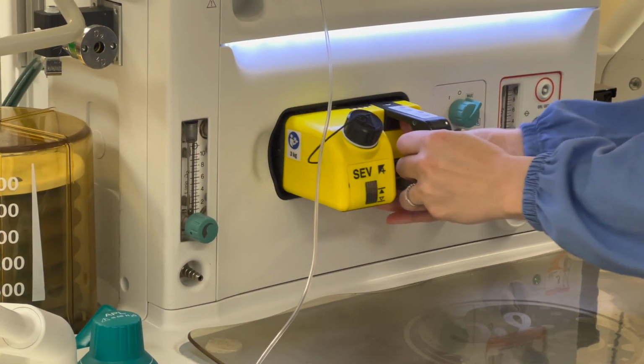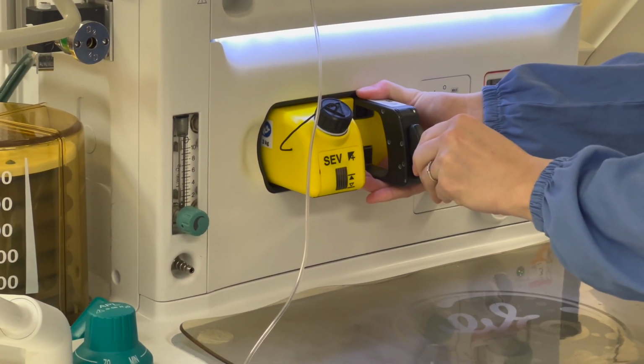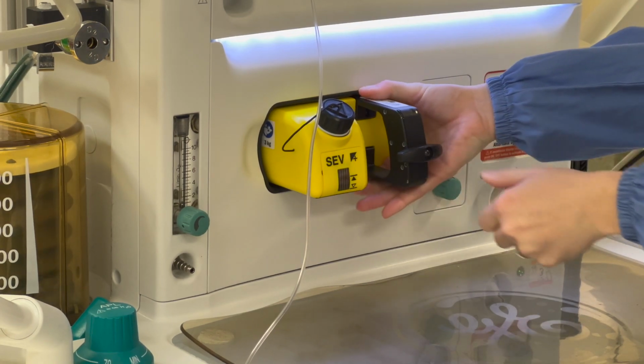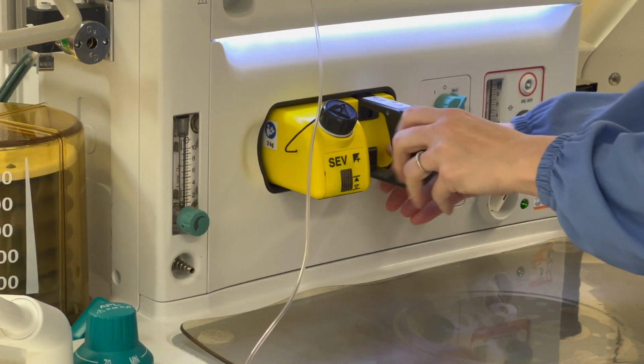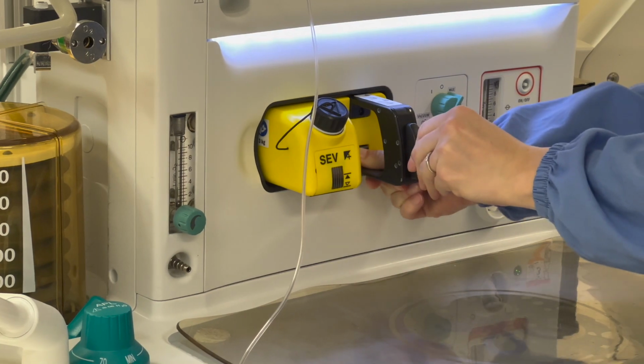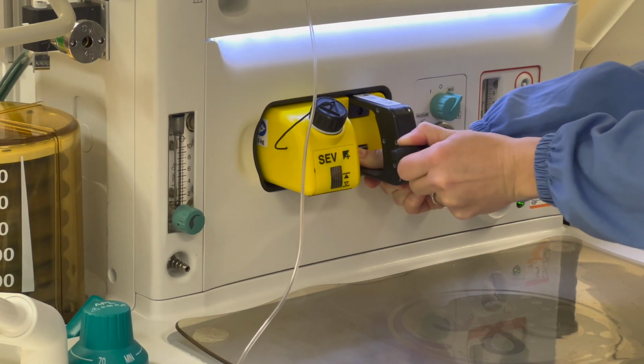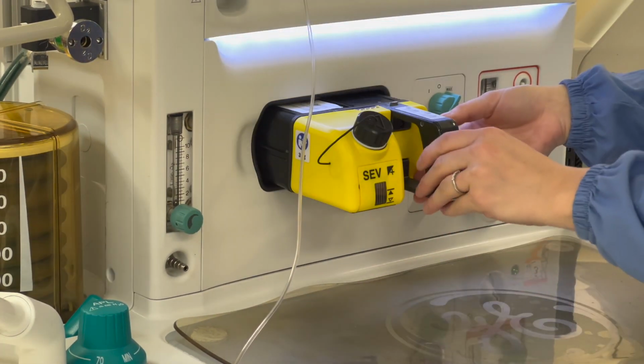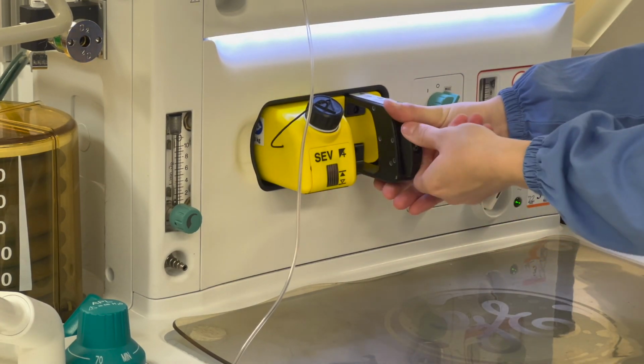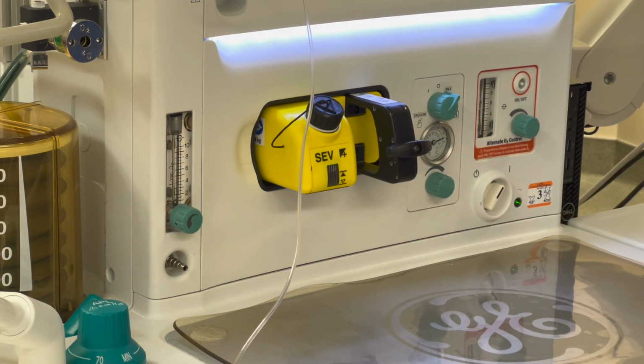One thing you may encounter is a cassette that doesn't fully engage. As you notice here, it slides back as you try to lock it in place. This won't be fully connected to the anesthesia machine, and it won't deliver anesthetic gases, and it'll be a potential for leak later on. Give it a firm push and then a twist, and it should stay in place.